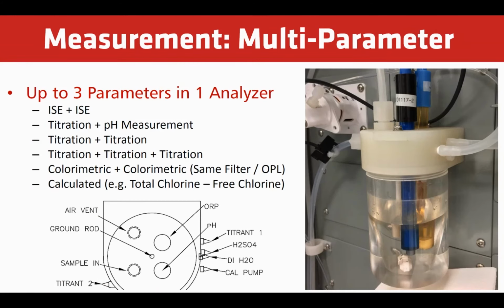We offer up to 3 parameters in one analyzer. For example, we can do a dual ISE analyzer. So we could offer nitrate, nitrite, or nitrate and ammonia in one analyzer, a titration and pH measurement if required, dual titrations, triple titrations, dual colorimetric analysis, or dual results from calculations. For example, we could do total chlorine and free chlorine on one analyzer.